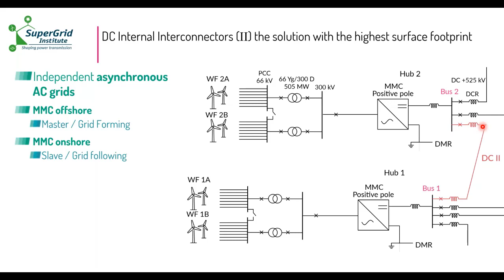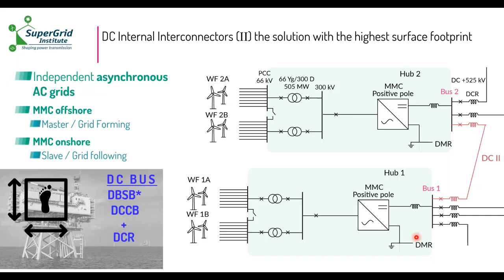So this final section is the technical presentation. It's the part for the comparison between AC and DC interconnectors. On the one side you have the DC interconnector option, in which you have a DC line connecting two MMC converters that are at the same time connecting to a wind farm collector grid. In this case, both AC collector networks are non-synchronous, so they are not connected in AC and they are not synchronized together. But in this case, you need to install what you need for protection of this DC line, that is the DC breaker and the DC reactor. So this now has to be included in the analysis, because as you may think, this is an offshore platform. If you put a breaker there, you're going to need space on the offshore platform, and this will be very costly. So this has to be assessed.